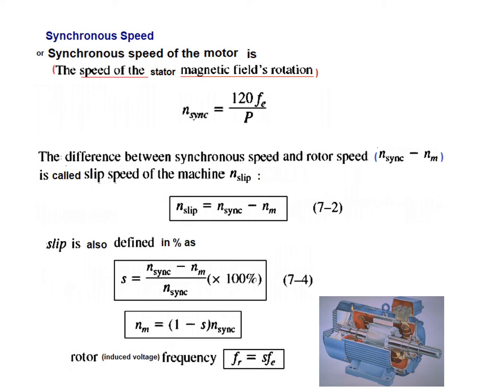Since the rotor lags the stator field, the frequency of the induced voltage in the rotor will be different from the frequency of the power supplied to the stator. That rotor frequency is given by: f_R = S × f_E, where S is the slip and f_E is the frequency of the applied signal.